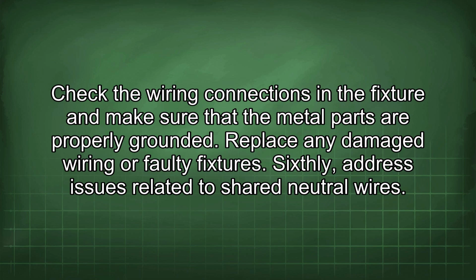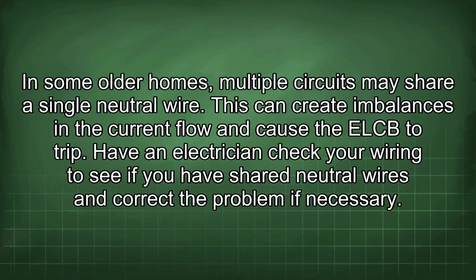Sixthly, address issues related to shared neutral wires. In some older homes, multiple circuits may share a single neutral wire. This can create imbalances in the current flow and cause the ELCB to trip. Have an electrician check your wiring to see if you have shared neutral wires and correct the problem if necessary.